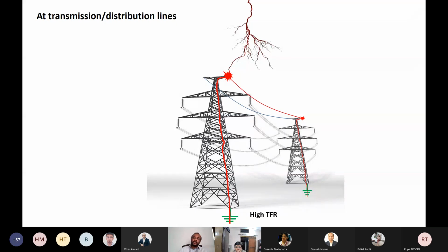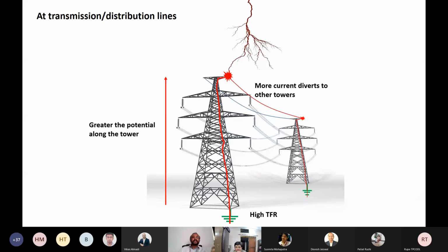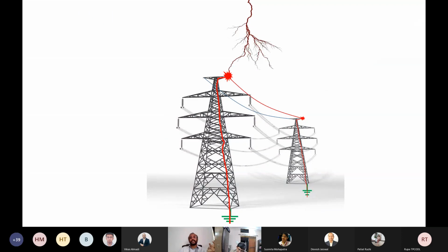Now, if the TFR, the tower footing resistance, is high, then what can you expect? Greater the potential along the tower, higher the TFR, so that more current diverts to other towers. So what you should understand is that if the TFR of a tower is high, then rather than the current flowing into that tower, larger components will go into the neighboring towers. Okay, now imagine that if the TFR is ultra high, now what happens?